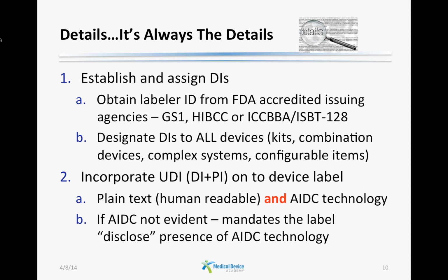When incorporating the UDI on a device label, it needs to be in human readable and AIDC technology format. The regulation does not specify a specific AIDC technology as it is technology neutral.